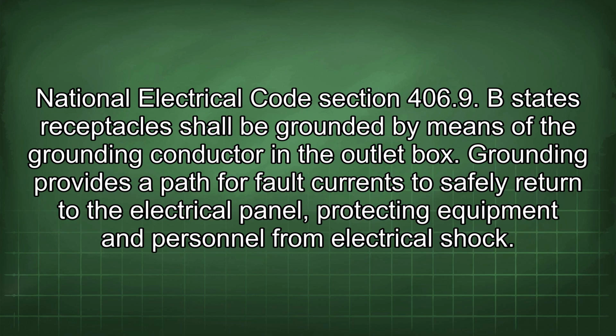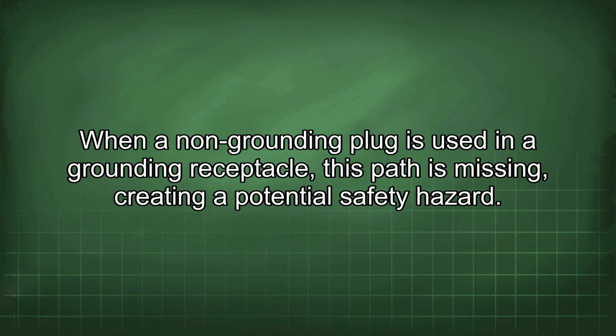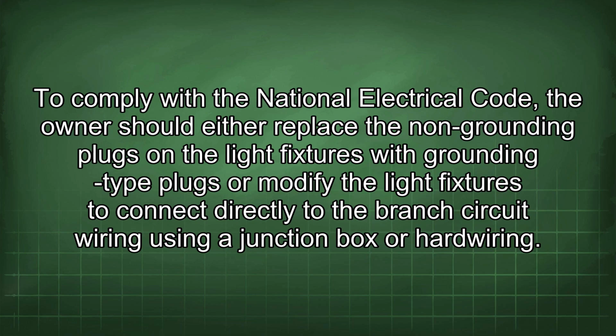Grounding provides a path for fault currents to safely return to the electrical panel, protecting equipment and personnel from electrical shock. When a non-grounding plug is used in a grounding receptacle, this path is missing, creating a potential safety hazard. To comply with the National Electrical Code, the owner should either replace the non-grounding plugs on the light fixtures with grounding-type plugs or modify the light fixtures to connect directly to the branch circuit wiring using a junction box or hardwiring.